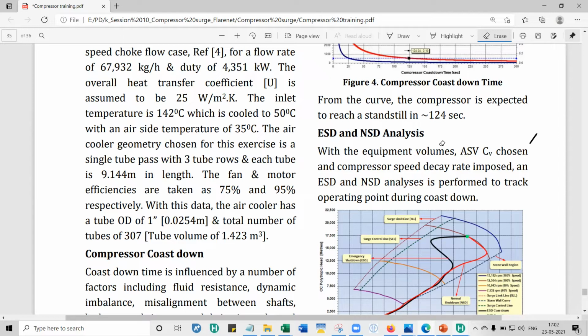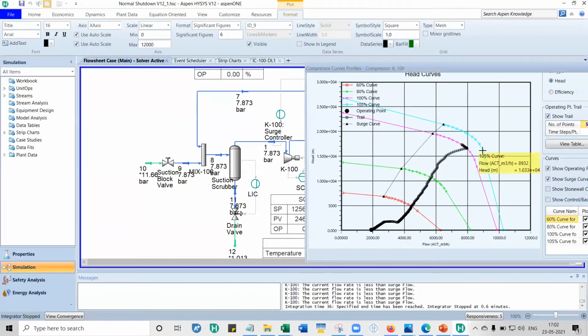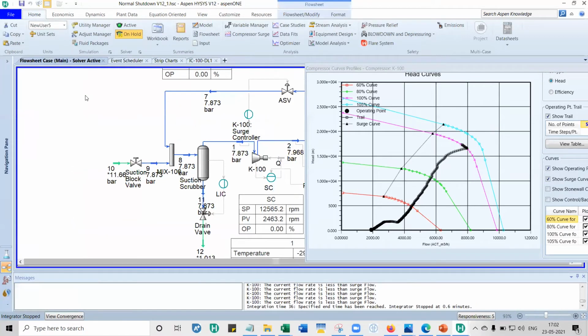Yes, that 100 CV that we used just now, you have already taken the snapshot also. There, if you see, the curve never went towards the right side. Here it is coming towards the right side, I can see, but in the previous one where 100 CV was used, the entire line was not coming towards the right. All are going towards the left. Completely, it has gone into surge. It's finished. Yes, we finished off the machine completely. Here, it is only a graph.